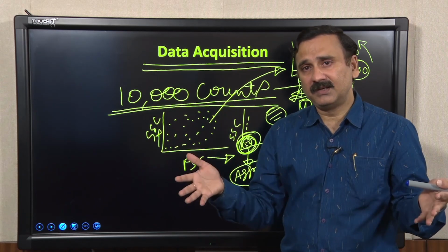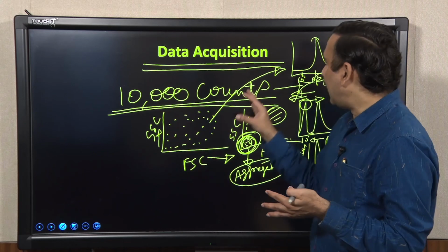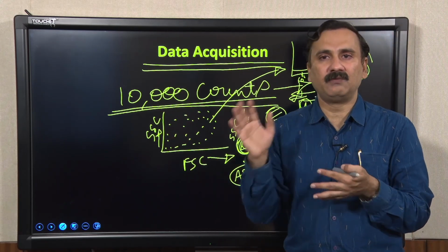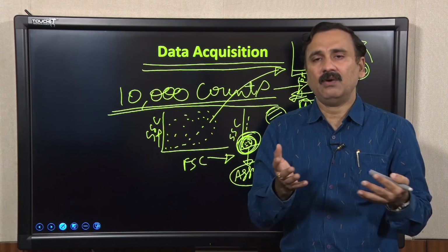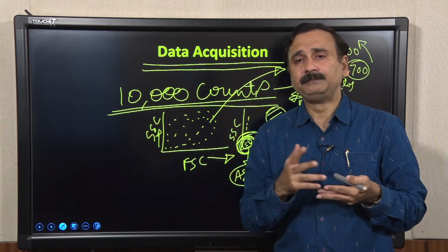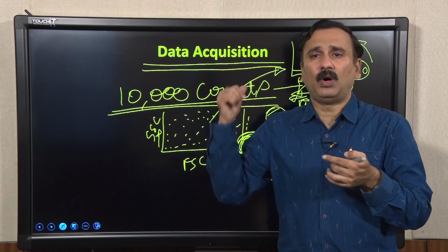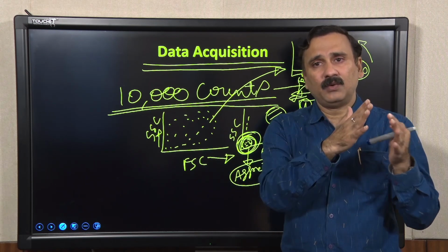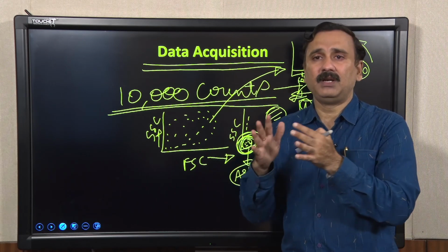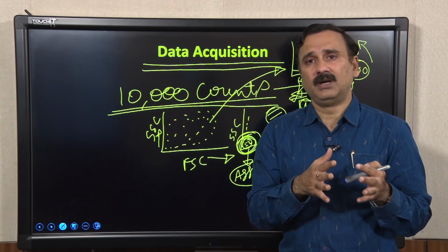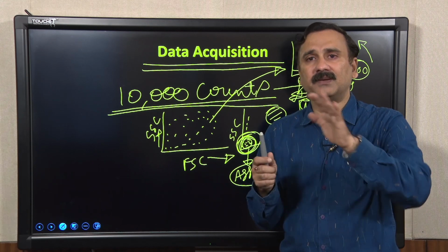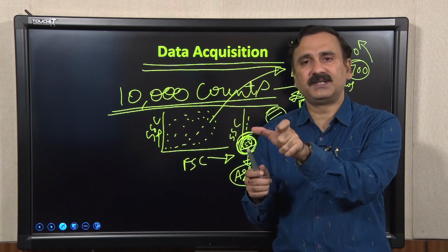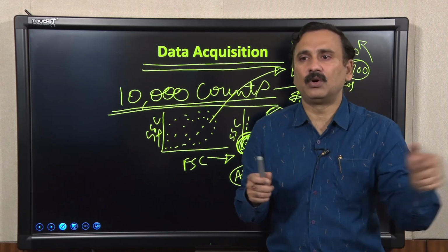Once you see a nice distribution, then you can ask whether the sample has a signal for FL1 or FL2 or FL3, or whatever fluorophore is present in your cells. Then you make all these modifications with the help of the voltage and gain, so that when you analyze the treated sample you are able to get the real picture. You should provide the flexibility in the system so that the treated sample can move towards the left or to the right.